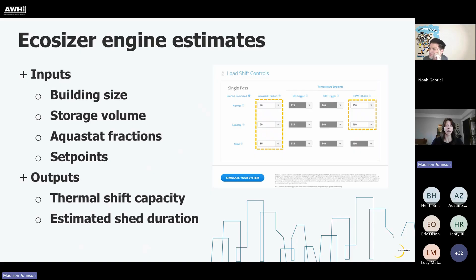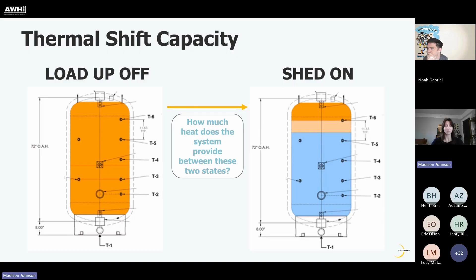Ecosizer also outputs the estimated shed duration, or length of time that we can expect the heat pump to remain off during a shed period that starts at 4 p.m. This metric is based on both the building size and the primary storage characteristics. While this tool was developed for the tech program, it's really valuable for predicting how much load shift capacity a system will have. And here's a visual representation of that thermal shift capacity. On the left, we have a snapshot of what our primary storage tanks look like at the end of a load up period, when our tank is fully charged. On the right, we have a snapshot of what the tank might look like at the end of a shed period, or when the heat pump needs to turn on during shed. So our thermal shift capacity tells us how much stored energy this system provided between this load up off state and the shed on state on the right.